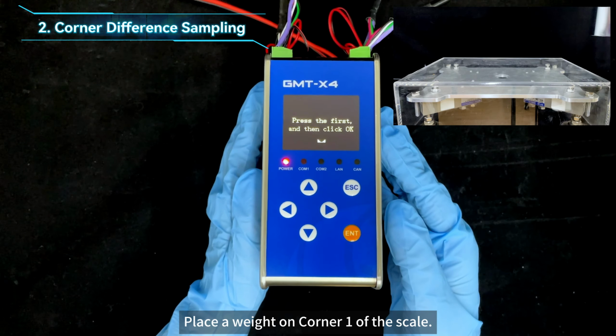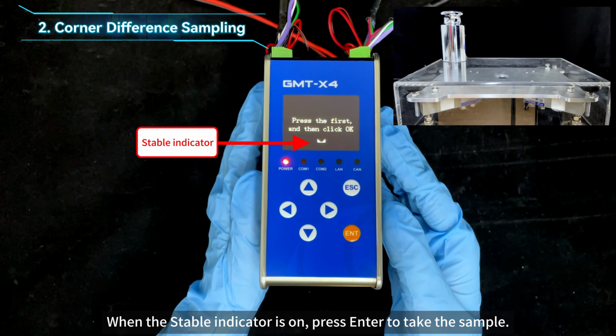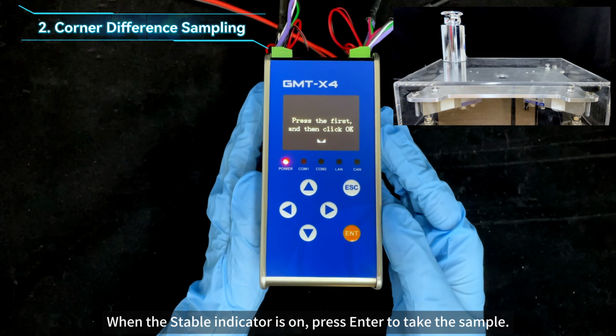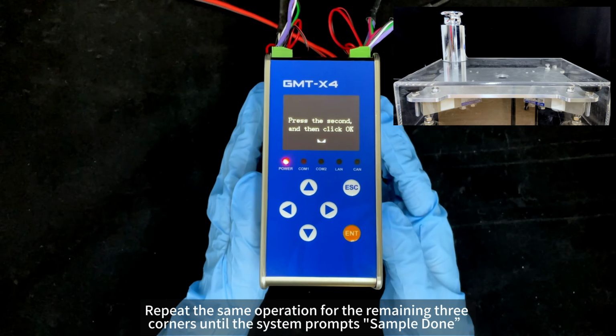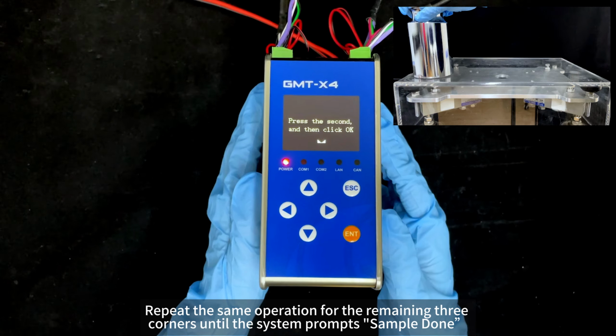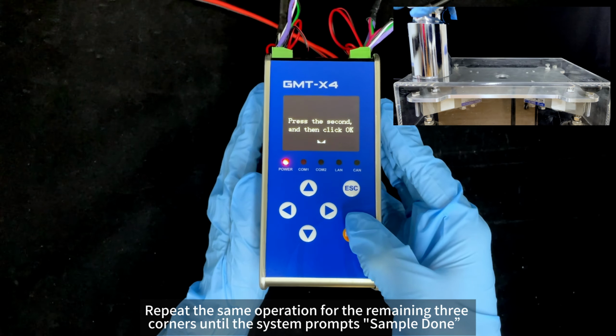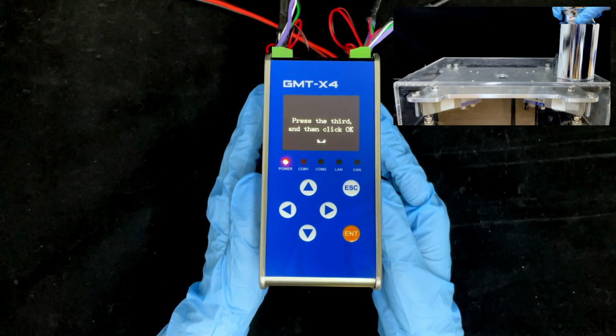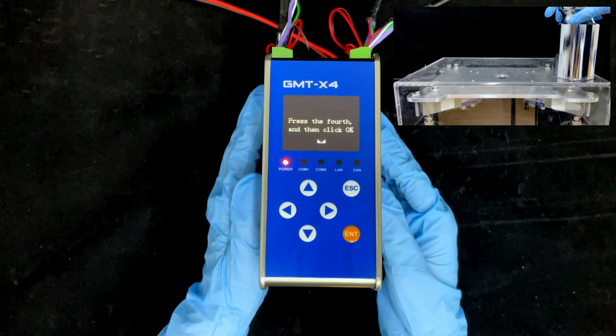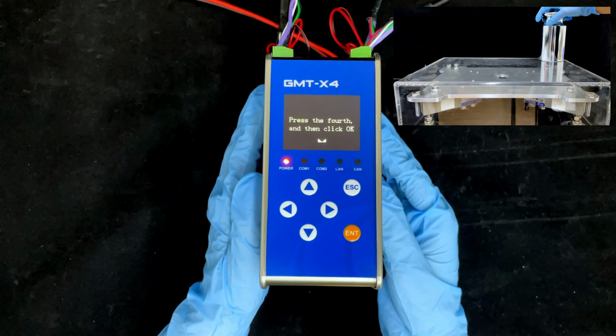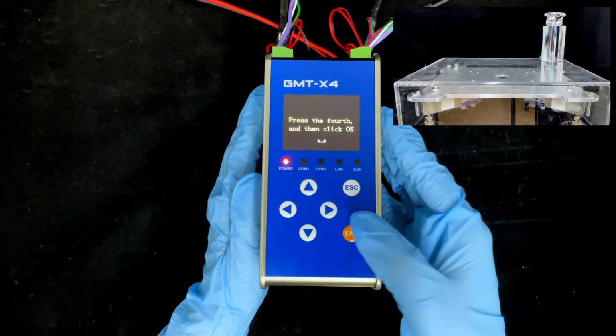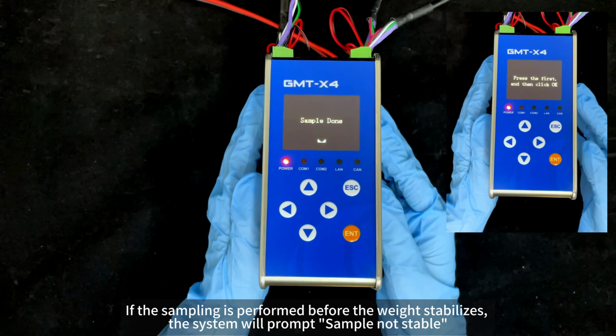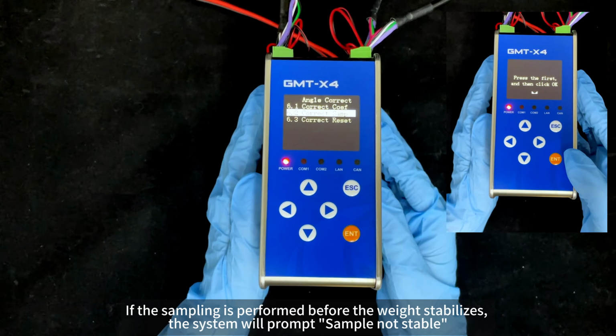Place a weight on corner 1 of the scale. When the stable indicator is on, press Enter to take the sample. Repeat the same operation for the remaining 3 corners until the system prompts Sample Done. If the sampling is performed before the weight stabilizes, the system will prompt Sample Not Stable.